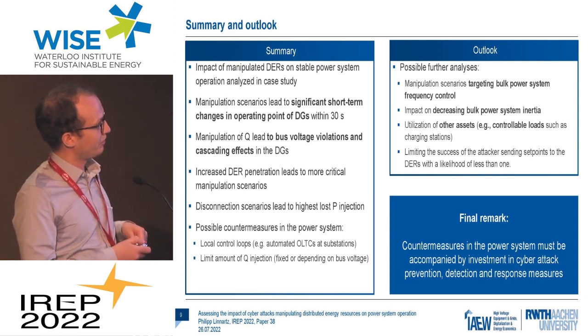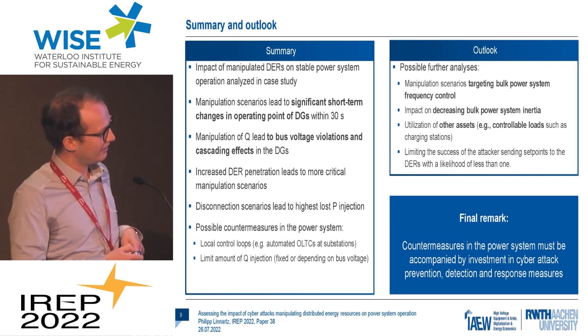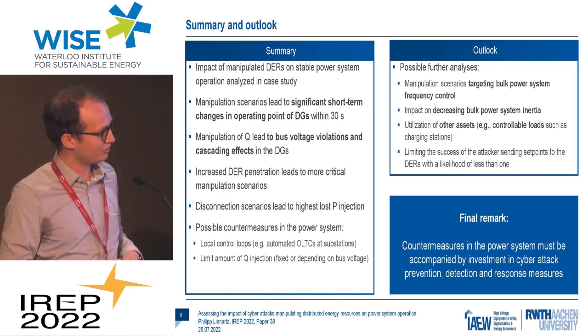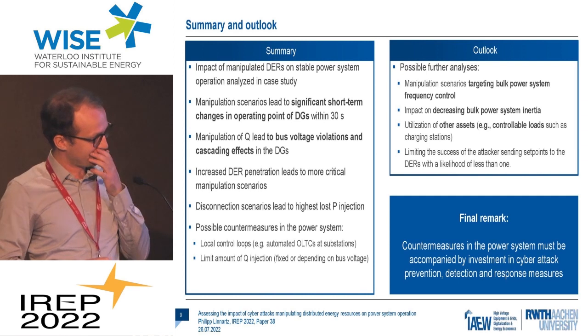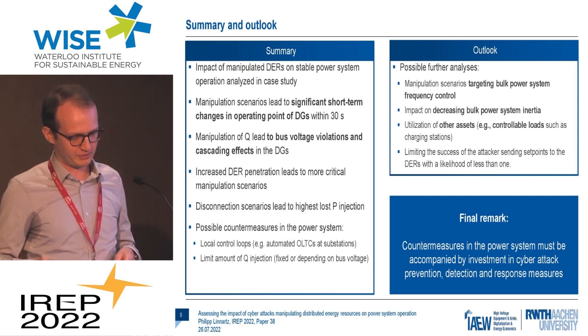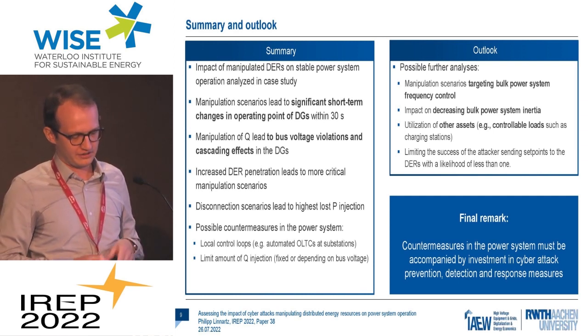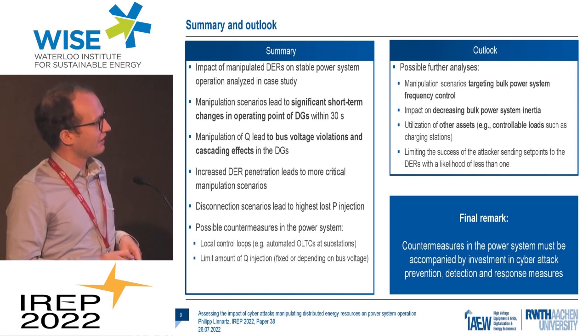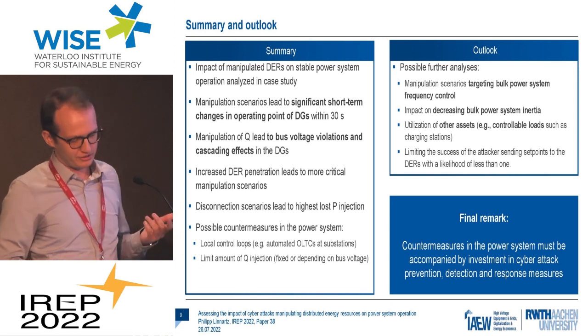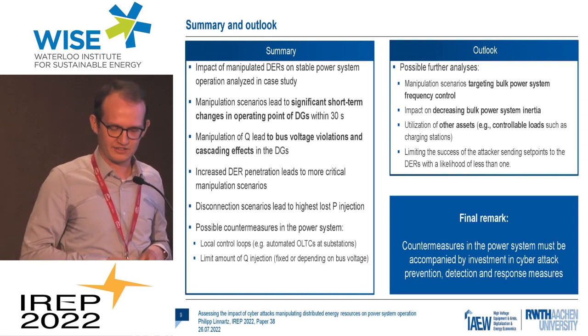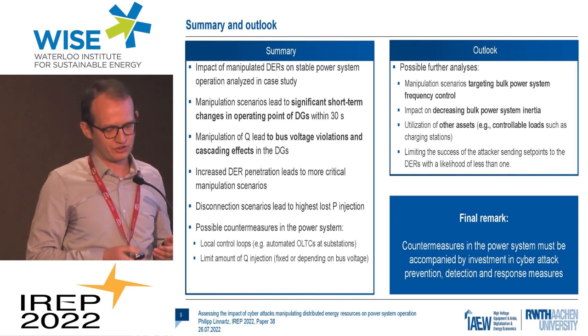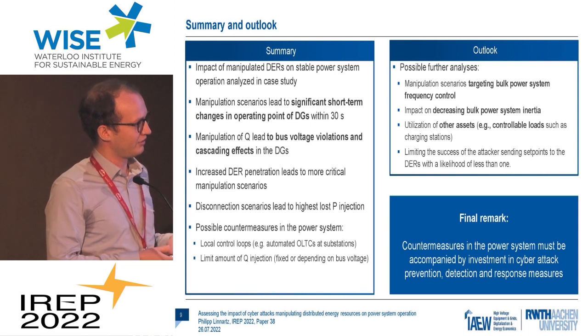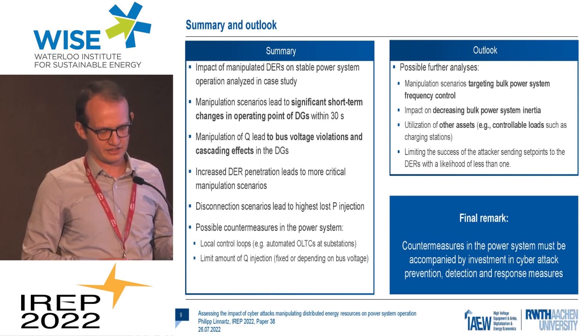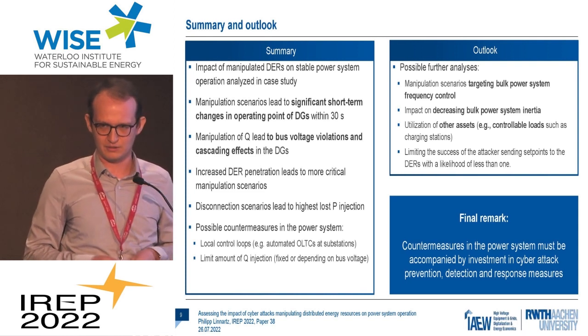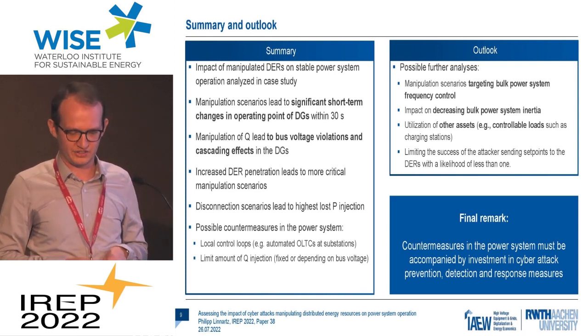I want to point out two countermeasures: local control loops not depending on central control, like automated OLTCs at the substation if we assume they just measure voltage at the lower voltage level. Also, limitation of the amount of Q injection accessible by central control, either by fixed values, or depending on bus voltages, so the DER rejects control commands if the bus voltage is outside the voltage band at the point where it receives.